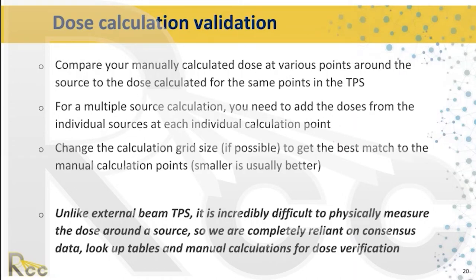It is strongly encouraged that every institution implementing a new brachytherapy treatment planning system perform an independent manual dose calculation to validate the TPS dose — both for commissioning and patient-specific QA. You can use the TG-43 formula for a simple first-order calculation or use available lookup tables, comparing manually calculated dose at various points around the source to those same points in the planning system. For multiple source calculations, doses from individual sources at each point are summed.